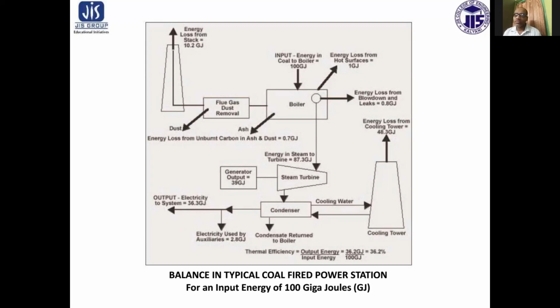So if we go for the balance, a total of 87.3 gigajoule of estimated energy is available at the steam turbine, as shown. Now, the generator output is 39 gigajoule, and the remaining heat goes to the condenser. The condensate is returned to the boiler; the condensate water is again fed into the boiler. In this process, electricity used by auxiliaries is approximately 2.8 gigajoule, and electricity to the system is 36.3 gigajoule. And the cooling tower, which is the major energy loss during the process, accounts for 48.3 gigajoule.